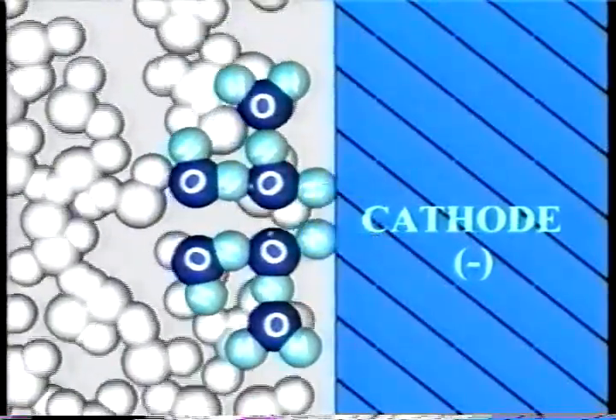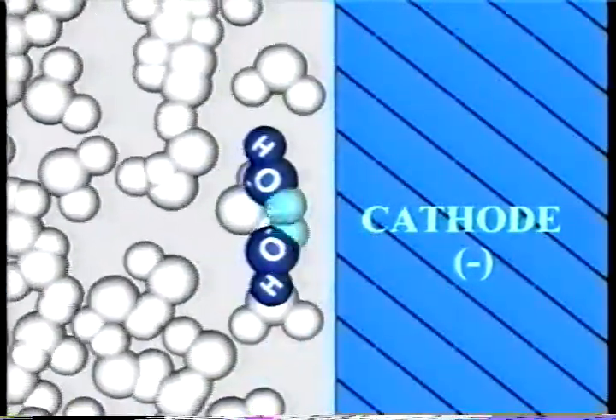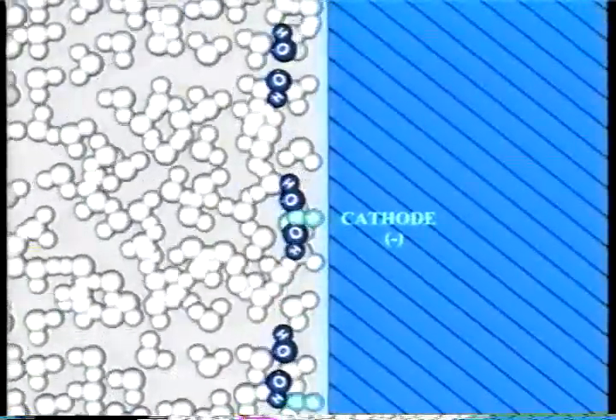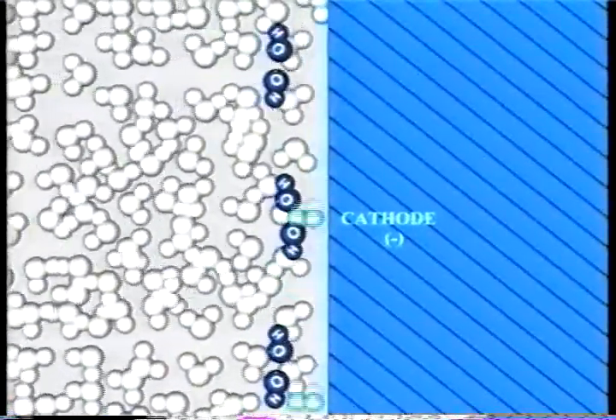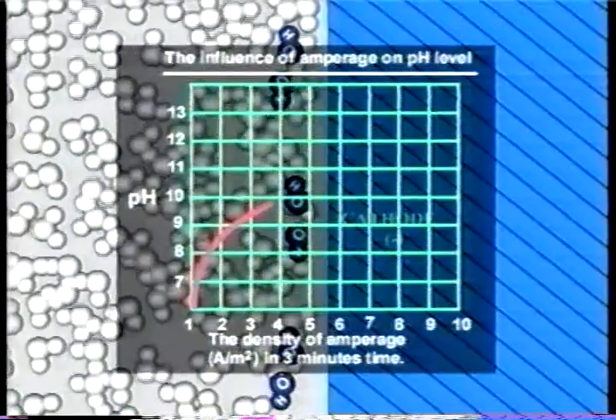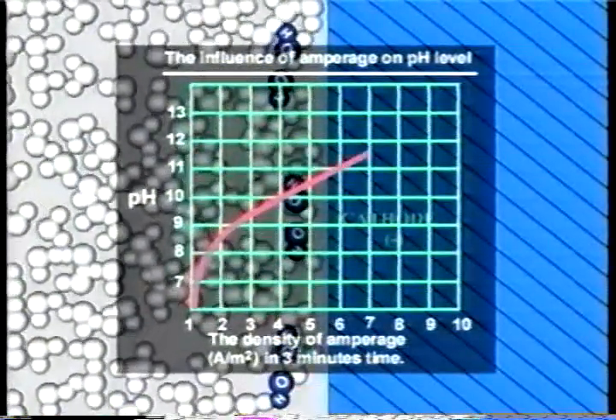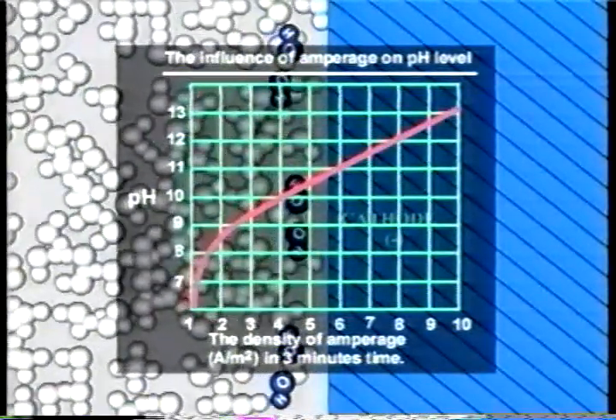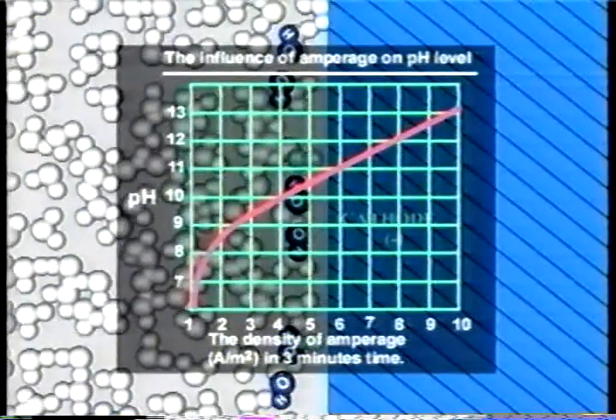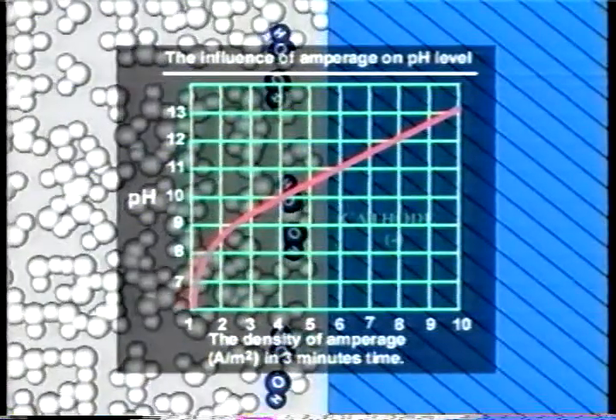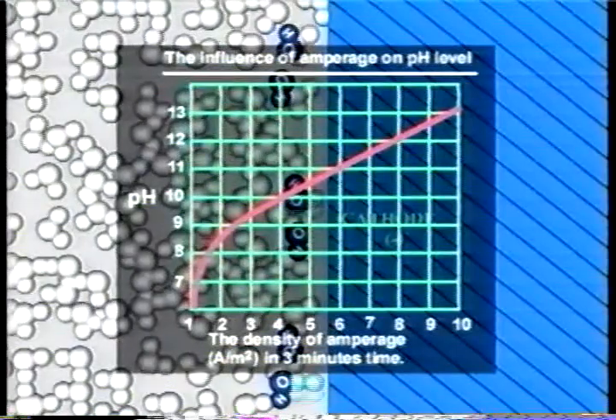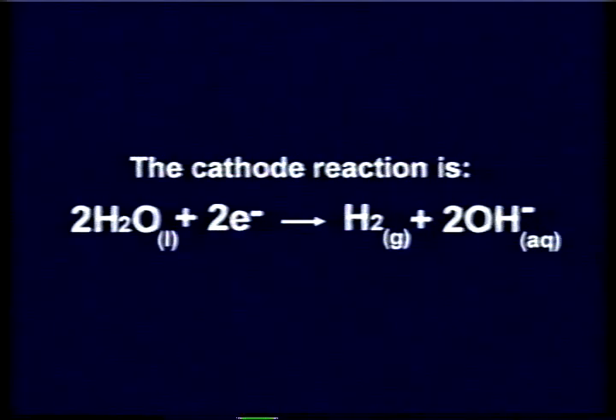The electrical current in the electrolysis system donates electrons to the water molecules adjoining the chamber walls that act as the cathode, causing the pH to rise to a level of 13 and hydrogen to be expelled. A computer continuously monitors this pH level in order to avoid reversing the polarity of the system, which causes corrosion.